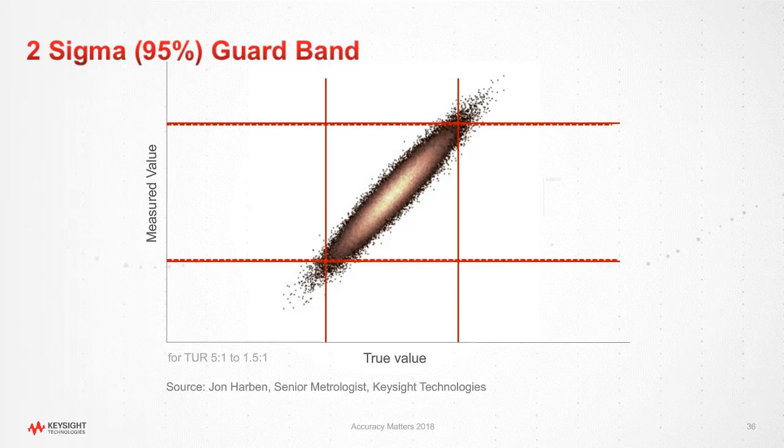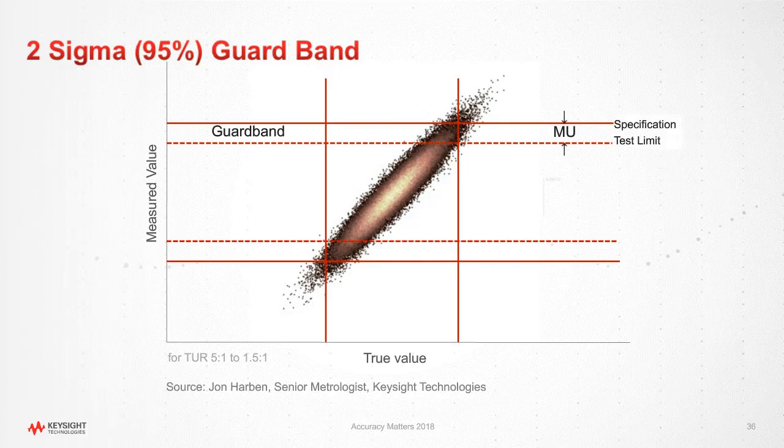If you do that, watch what happens now. You can see that we've lowered the guard band. And so now what remains of false accepts is what's below the dotted line. And the good news, it's really small. It's less than 0.15%. Now, before you celebrate, notice what else happened. If you say that everything above the dotted line fails, look at that.